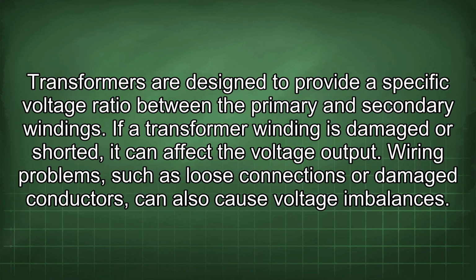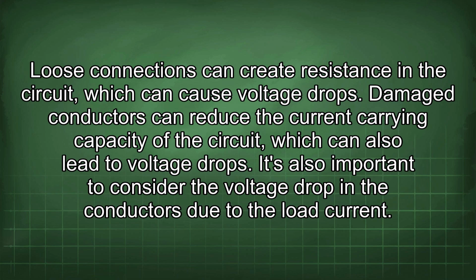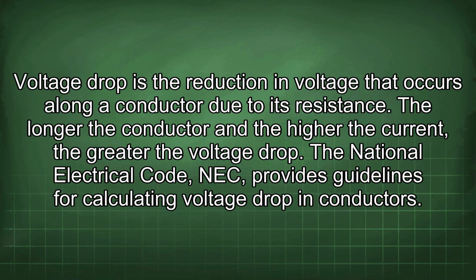Transformers are designed to provide a specific voltage ratio between the primary and secondary windings. If a transformer winding is damaged or shorted, it can affect the voltage output. Wiring problems, such as loose connections or damaged conductors, can also cause voltage imbalances. Loose connections can create resistance in the circuit, which can cause voltage drops. Damaged conductors can reduce the current carrying capacity of the circuit, which can also lead to voltage drops. It's also important to consider the voltage drop in the conductors due to the load current. Voltage drop is the reduction in voltage that occurs along a conductor due to its resistance. The longer the conductor and the higher the current, the greater the voltage drop. The National Electrical Code, NEC, provides guidelines for calculating voltage drop in conductors.